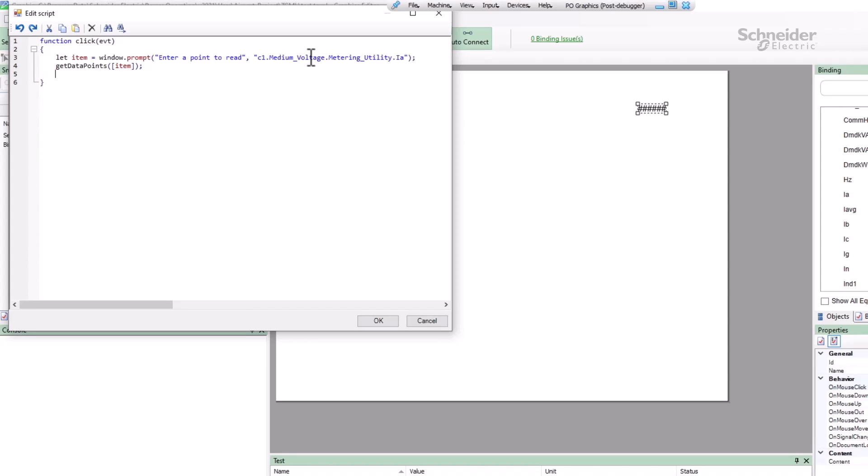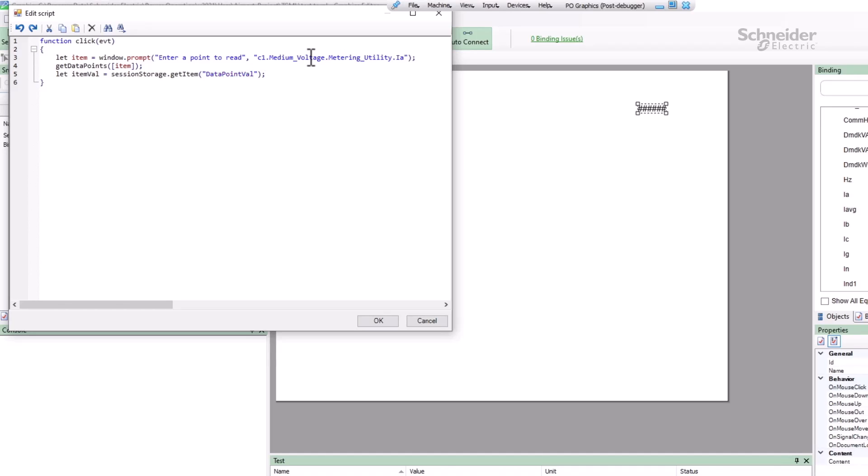To receive the value, the WebHMI stores the server's response in a global object called sessionStorage that we'll see again in the future. To retrieve it, I'll call sessionStorage.getItem and pass it the string DataPointVal. This is the key in the sessionStorage object where my variable is stored. Note that I said GetDataPoints takes a list of items. If I pass more than one item, DataPointVal will be a comma-separated string of my return values in order.